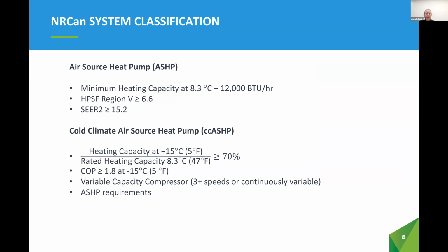As part of the Greener Homes Initiative, Natural Resources Canada classified eligible air source heat pumps using the following performance criteria. We use the same criteria in the Efficiency Manitoba heat pump rebate to determine the difference between standard and cold climate air source heat pumps. You'll notice that the cold climate units have 3 additional criteria: heating capacity maintenance, which results in less of a capacity drop-off at colder temperatures; minimum coefficient of performance at colder temperatures; and variable speed compressors.